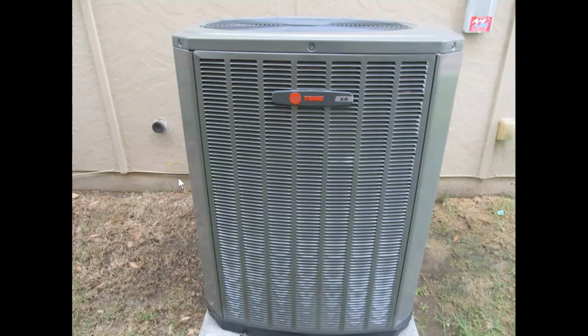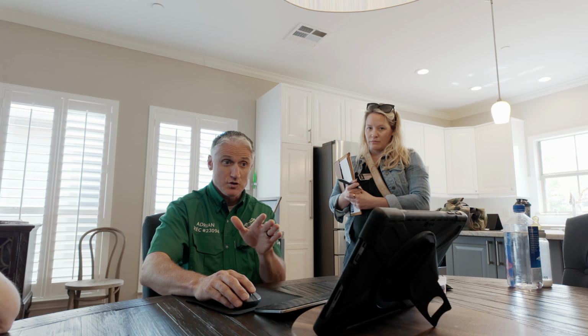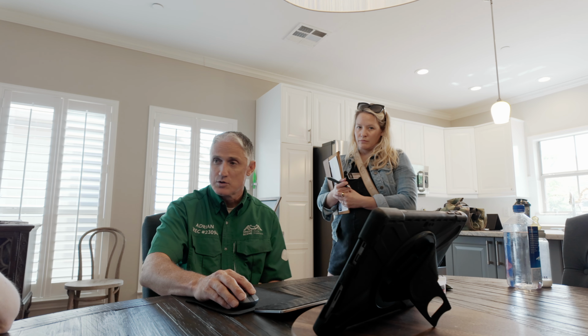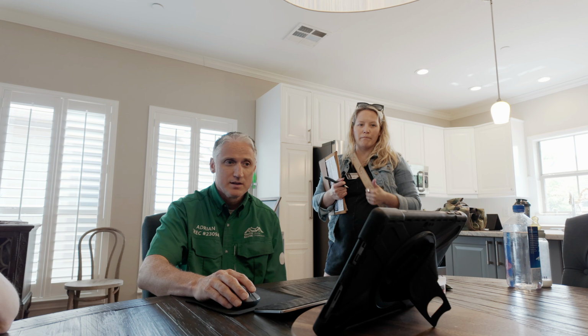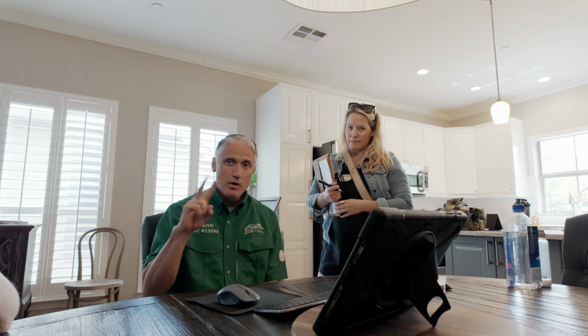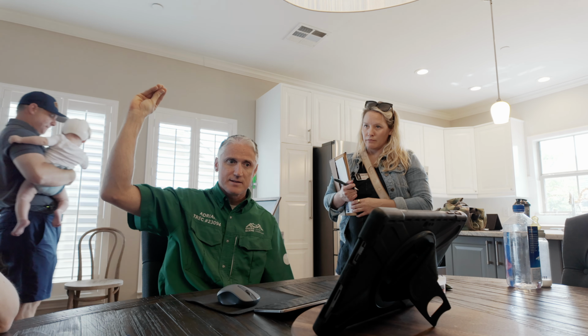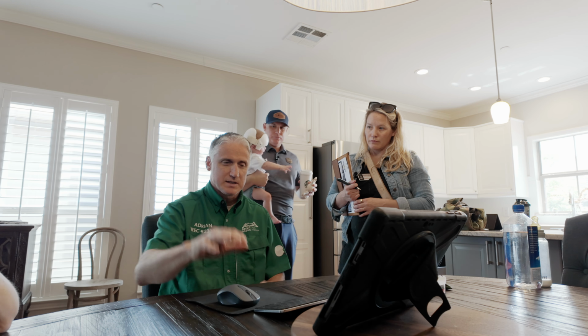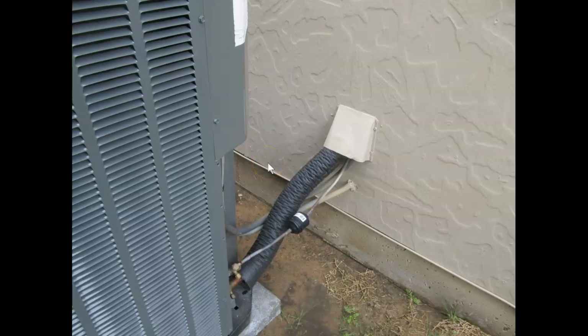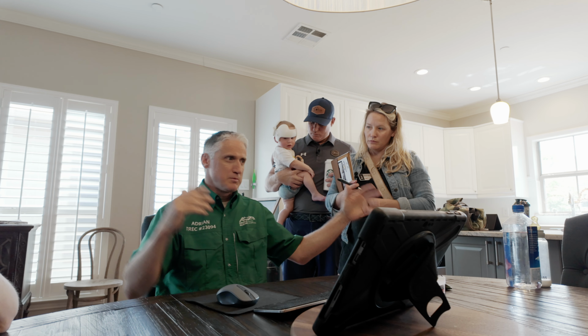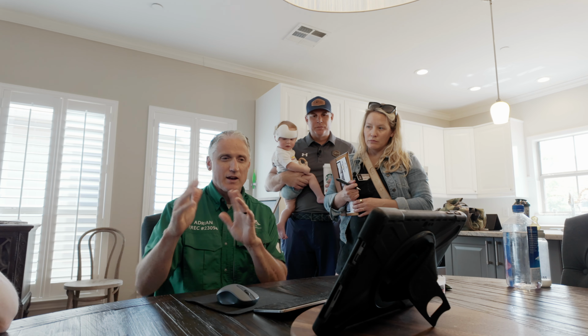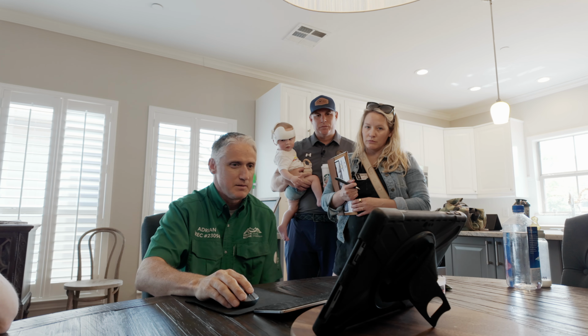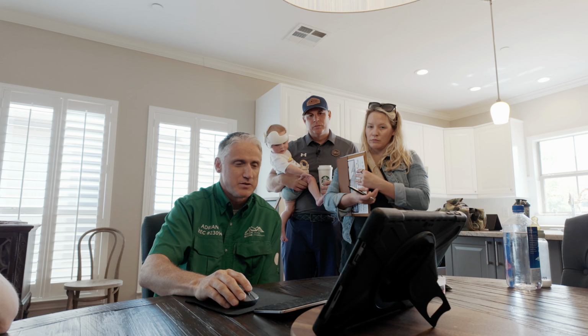Then I'm going to start with your outside air condenser. It's a Trane, basically brand new, a 2024, so that's good. It's 5 ton in size. You have one unit but 2 thermostats. Remember that, because I'm going to come back to the thermostat issue in a second, since you may have felt some temperature differences going into the bedroom versus downstairs and upstairs. I think I know what's going on 90% of the way there, at least enough to point you in the right direction.